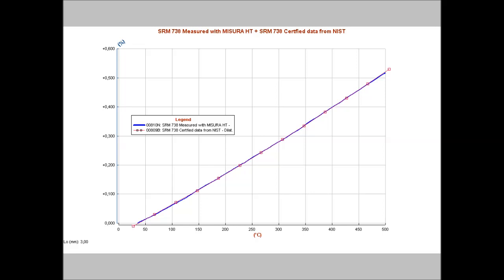For this reason, it is absolutely necessary to apply a correction curve, which accounts for the expansion of the measuring system. In the optical dilatometer, the sample is completely free, and it is not necessary to record and use the procedure of the calibration curve. This graph is showing the result of the measurement of the standard reference material 738, the blue line, supplied by the National Institute for Standards and Technology, NIST, in comparison with the data certified by the NIST, the red dotted line. Since it is not necessary to correct the curve with the correction curve, it becomes possible to use complex heating and cooling rates during the test. This makes it possible to reproduce industrial firing cycles.